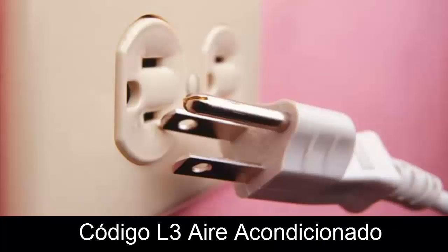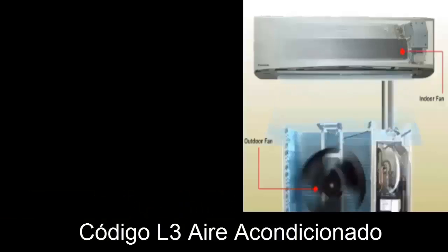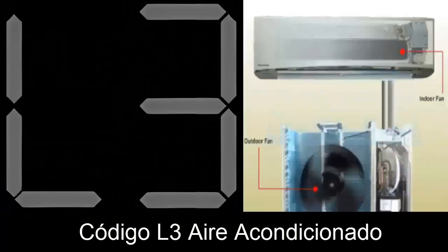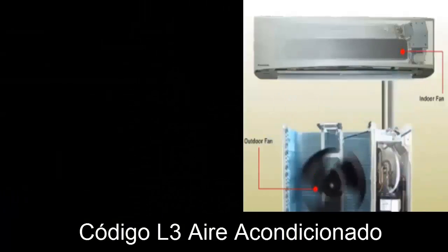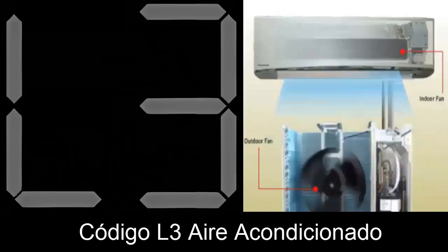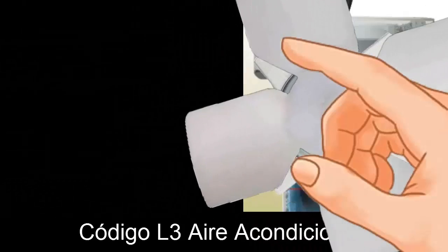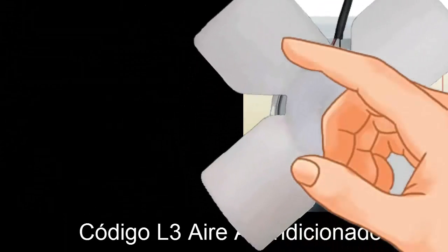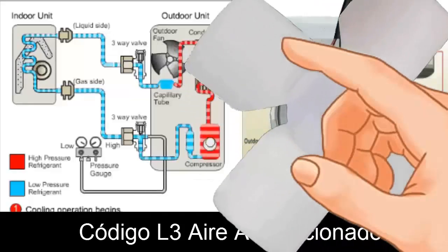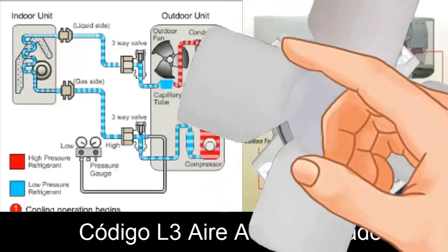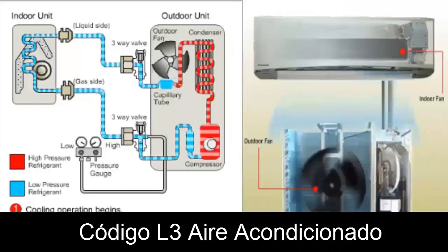Steps to diagnose and solve the L3 error. 1. Disconnect the unit from the power supply and see if the error persists. 2. If the error persists, disconnect the unit again and check the fan's movement. Ensure that the fan and blades of the external unit move properly. If the fan moves correctly, it rules out issues with blockage and motor shaft bearings.